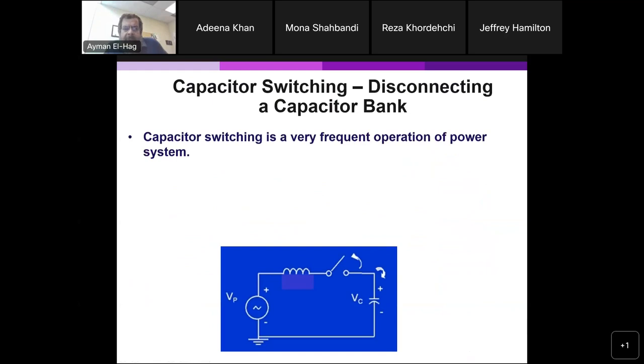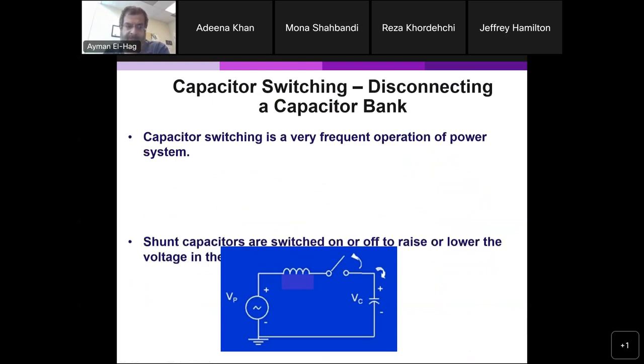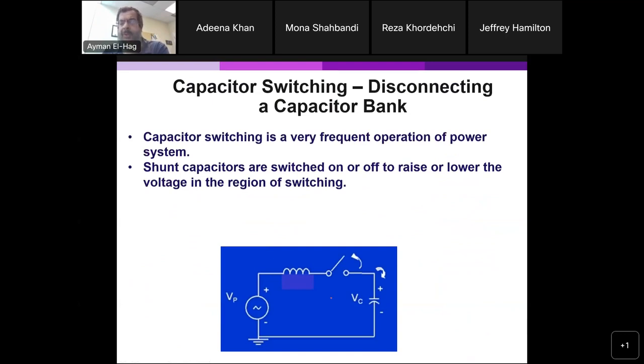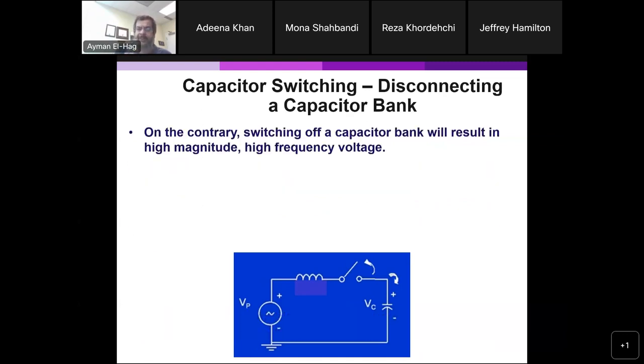The second abnormal transient is due to capacitor switching. As I mentioned last week, capacitor switching is very common. We switch capacitors on and off to improve power factor — they are connected as shunt elements in parallel with loads. We switch them on when power factor is low, and off to avoid leading power factor. When we switch on a capacitor, we introduce high voltage and high frequency. When we switch off the capacitor, this results in even higher voltage and high frequency.